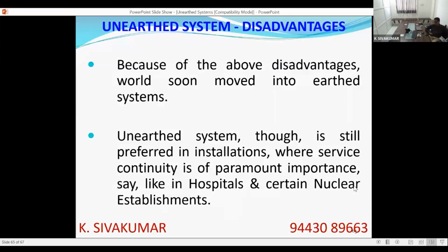Unearthed systems, yes, there are certain installations where service continuity is of paramount importance, say in hospitals, where operation theaters or critical diagnostic equipment are there. They don't want power interruption during a surgery or during a diagnostic where the results may be tilted. So for locations where service continuity is important, people still go for unearthed systems. In such cases the network itself is split with separate transformers. One transformer with an earthed system for the normal system, and one transformer with isolated neutral for special areas like hospitals, operation theaters, diagnostic rooms, and certain nuclear establishments also. They don't want supply continuity to be disrupted. So unearthed systems are now confined to very minimal locations.